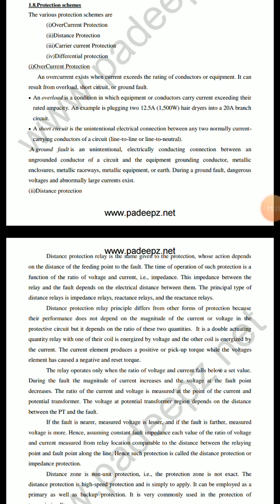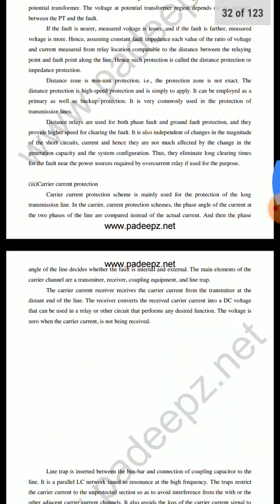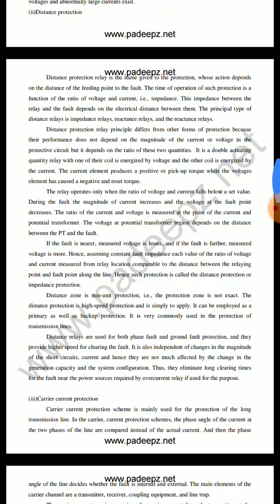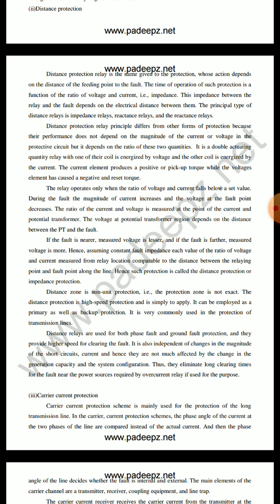Here are some of the protection schemes: overcurrent protection, distance protection, carrier current protection, and differential protection. In overcurrent protection, the actual power supply is compared with the rating, and if it exceeds the possible rating, an overload may occur, and at that time the protection process operates. The next one is distance protection. For a transmission line, because of the distance, we need to protect with distance protection over the long distance itself. In case a fault occurs on the line, the connected relay will signal the circuit breaker, and the remaining protection process follows.